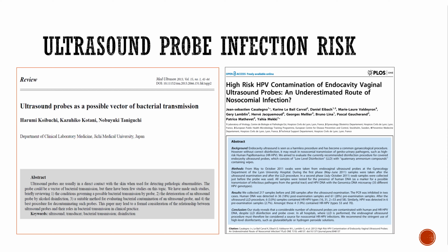Another study, which I think really highlighted some of the issues particularly around vaginal ultrasound probes, was the risk of HPV contamination, and that this was not a well-recognized method of transmission. We came to understand that many of the ways that we were previously disinfecting were inadequate against this particular virus, the HPV virus.